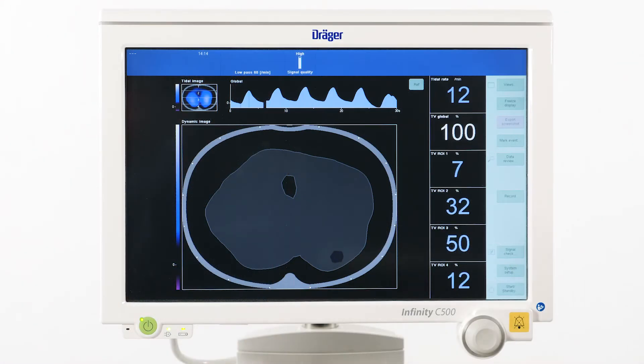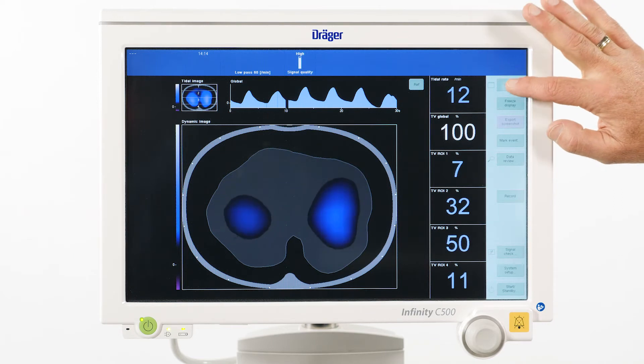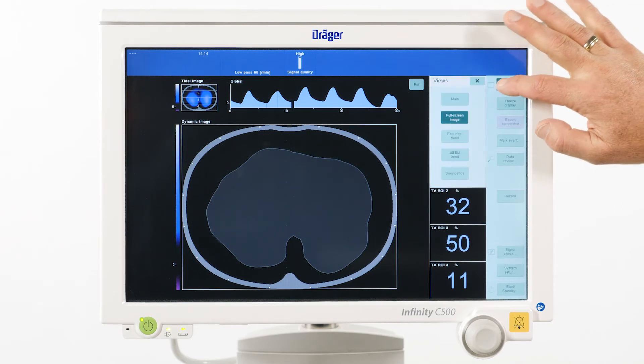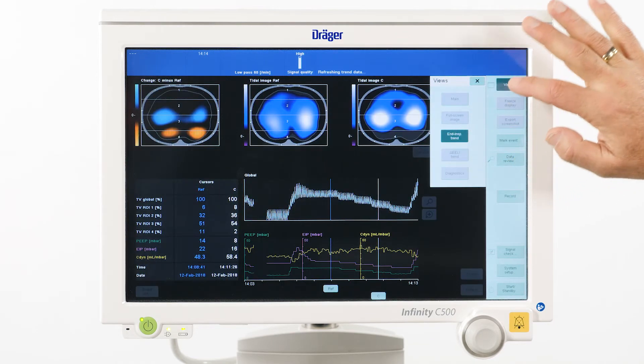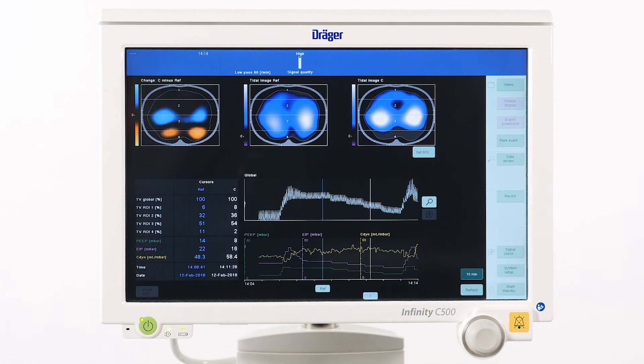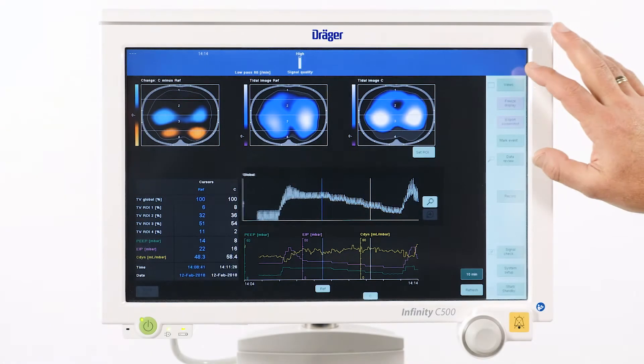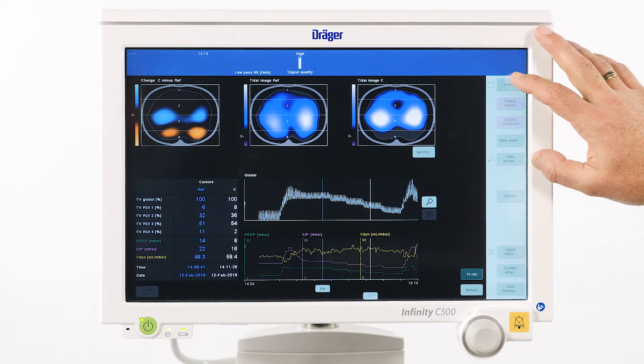Assessing therapeutic interventions requires the display of trended data, which isn't really a new feature of PulmoVista. The very exciting feature of this new diagnostic view is a highly elaborated algorithm which scans the entire trend data for the characteristic patterns of a decremental PEEP trial.